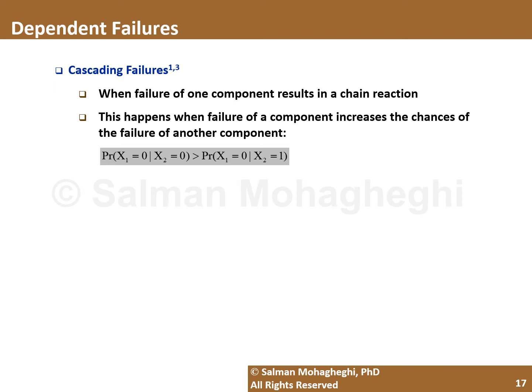Mathematically, we can say that cascading failures occur when the likelihood of failure of a component increases when another component has failed. Imagine x1 = 0 indicates the failure of a particular component. So the probability that component 1 fails, given that component 2 has already failed, is higher than the probability of component 1 failing, given that component 2 is operational. Meaning that if component 2 fails, it will increase the likelihood of component 1 failing. If this criterion is met, the conditions are set for some sort of cascading failure. There are a lot of situations in power systems in particular when cascading failures may occur.